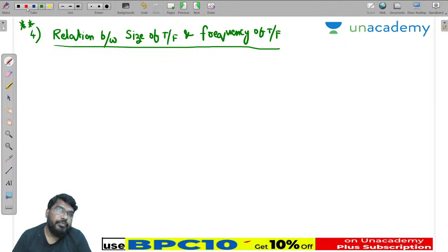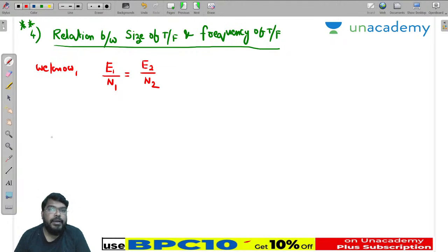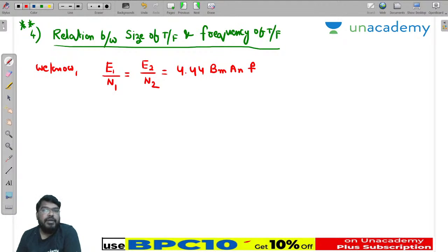We know the EMF per turns ratio in the primary winding, E1 by N1, is equal to the EMF per turns ratio in the secondary winding, E2 by N2, which equals 4.44 B maximum A N f. This is our relation.